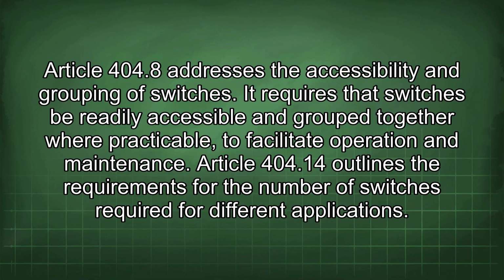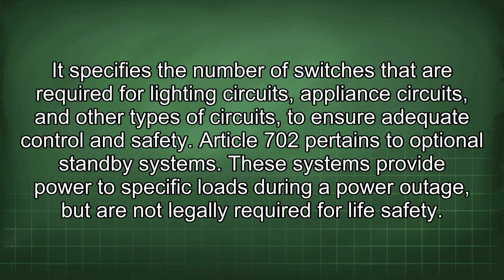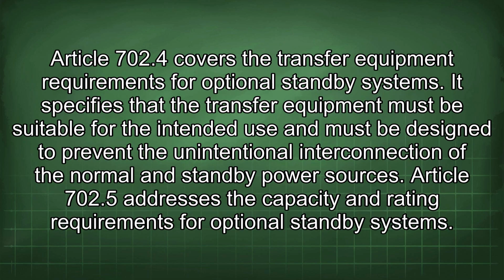Article 404.14 outlines the requirements for the number of switches required for different applications. It specifies the number of switches that are required for lighting circuits, appliance circuits, and other types of circuits to ensure adequate control and safety. Article 702 pertains to optional standby systems. These systems provide power to specific loads during a power outage, but are not legally required for life safety. Article 702.4 covers the transfer equipment requirements for optional standby systems.